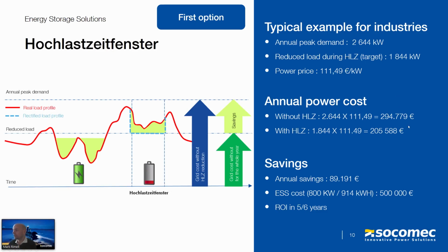So when we provide our calculations, without the Hochlastzeitfenster scheme, our grid fees are 294,000 euros per year. If we then participate in the Hochlastzeitfenster scheme and reduce our peak during this period that is defined by the grid operator, our fees would actually be reduced to €205,000 per year, providing an annual saving of €89,000. So in order to achieve this, we have sized the battery system based on 800 kilowatts. This would be the difference between our annual peak demand and our reduced peak demand of 1,844. You can see an 800 kilowatt deviation to last for approximately 1 hour. The budget price for this is €500,000, which ultimately is providing our customers with a return on investment within 5 to 6 years.